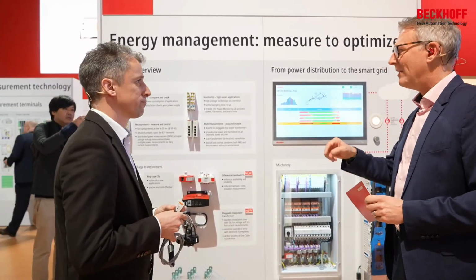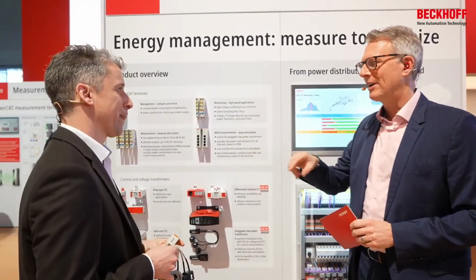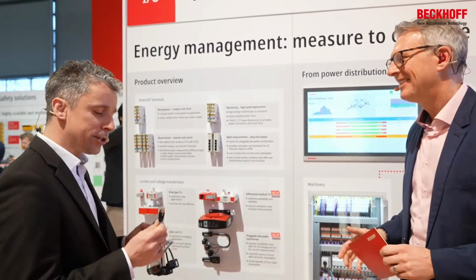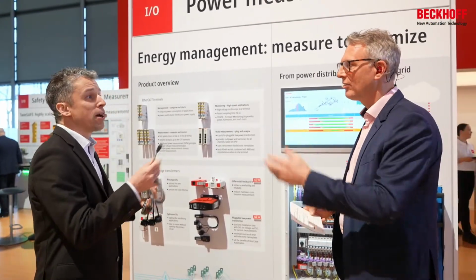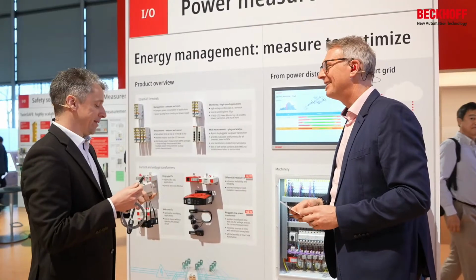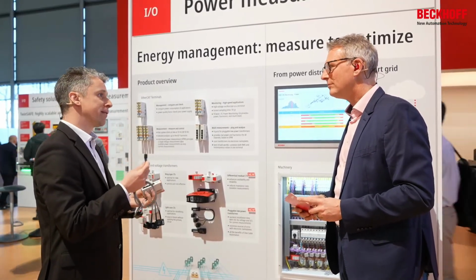Yeah, but why the hell do you connect an RJ45 to a terminal to measure power? I don't get it. Usually these cables are for internet, let's say. Or Ethernet. Right. But in this case, it's not. So here we use 330 millivolt 3 times for 3 current transformers.